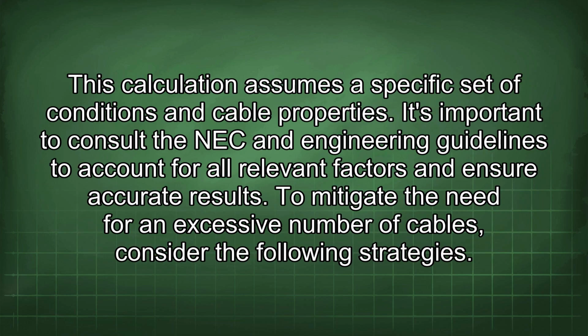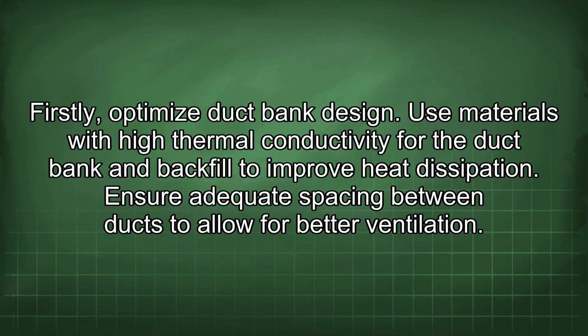This calculation assumes a specific set of conditions and cable properties. It's important to consult the NEC and engineering guidelines to account for all relevant factors and ensure accurate results. To mitigate the need for an excessive number of cables, consider the following strategies. Firstly, optimize duct bank design. Use materials with high thermal conductivity for the duct bank and backfill to improve heat dissipation. Ensure adequate spacing between ducts to allow for better ventilation.